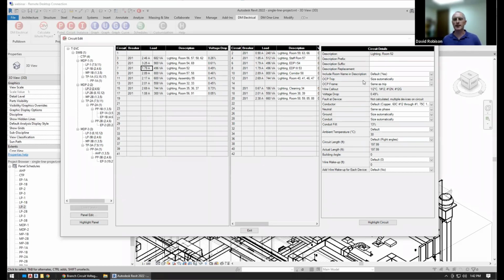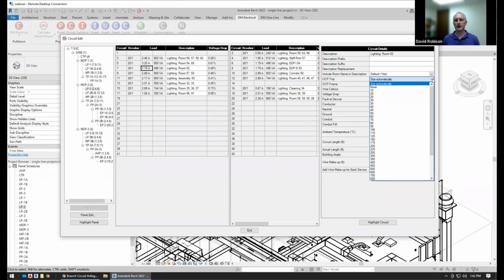The first thing we'll take a look at is the overcurrent protection trip size. By default, everything is set to size automatically, so it's actually pulling the size for the overcurrent protection from elsewhere in the project. You can override that. You can set it to none if you don't want a breaker, or you can set a specific breaker size, and then it'll use that for the breaker size. And if the wire is sizing automatically, it'll size the wire to match.